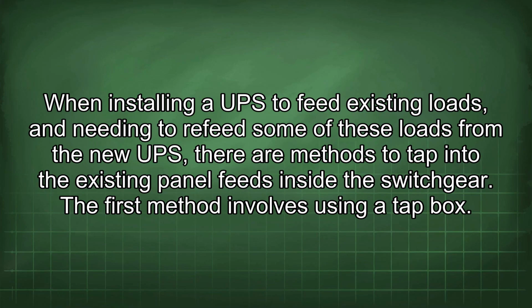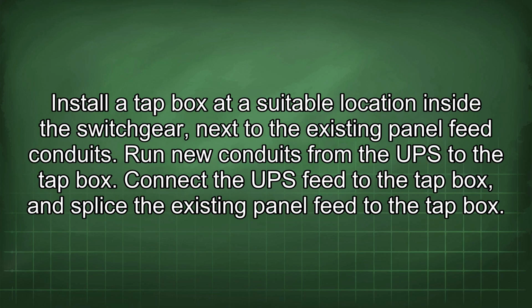When installing a UPS to feed existing loads, and needing to refeed some of these loads from the new UPS, there are methods to tap into the existing panel feeds inside the switchgear. The first method involves using a tap box. Install a tap box at a suitable location inside the switchgear next to the existing panel feed conduits.